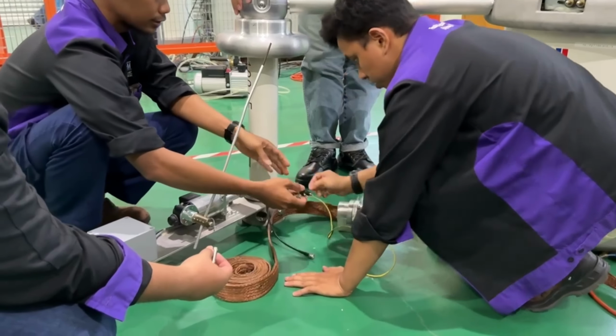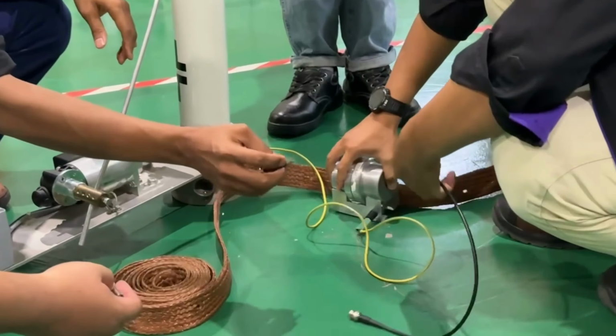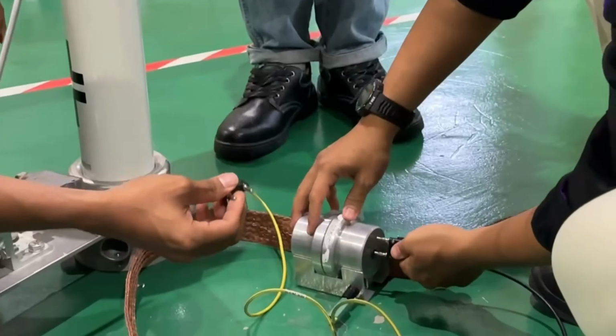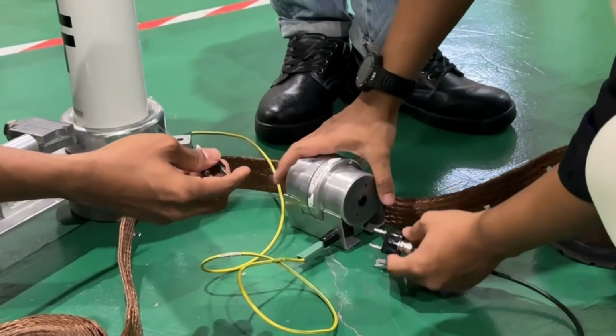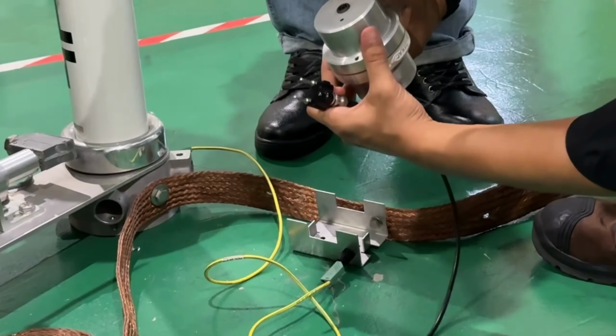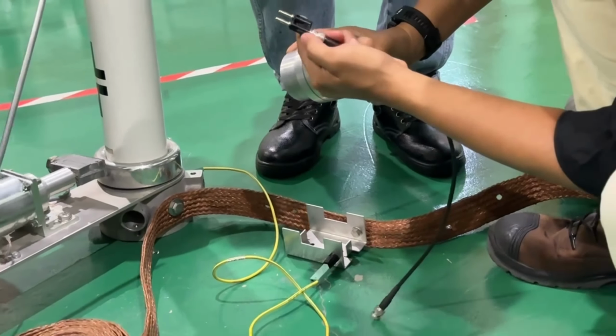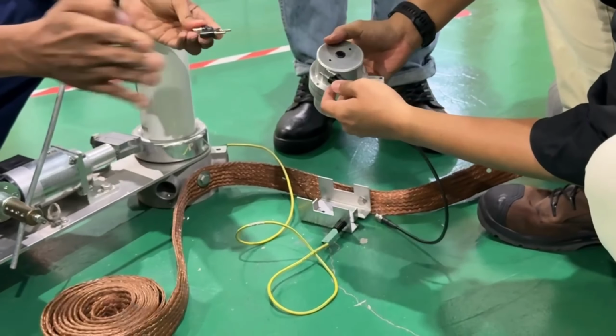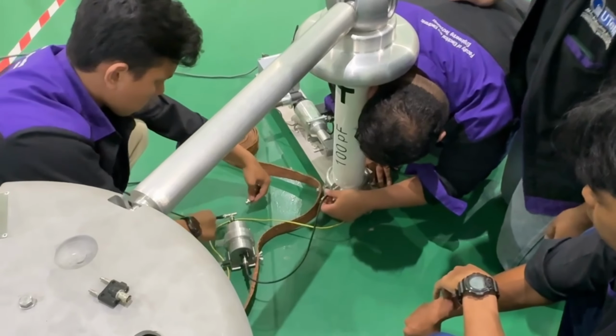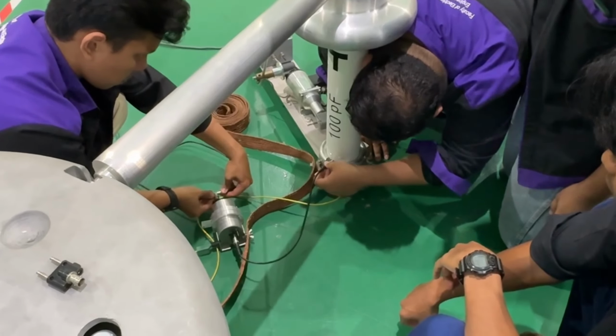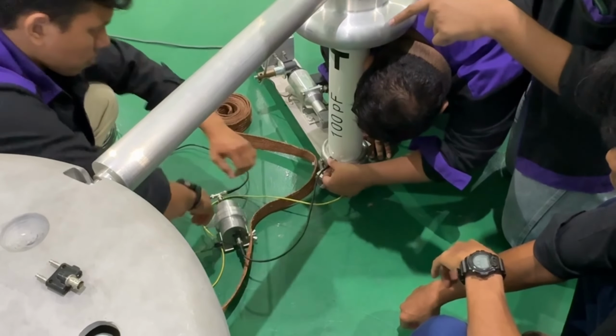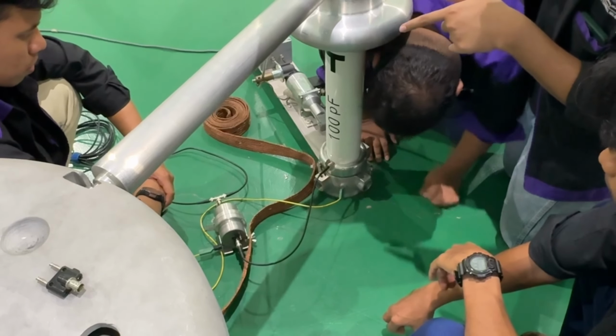So for the CB impulse connection, connect the male coaxial cable with the capacitor. Locate the two ports of the CB impulse unit. At the first port, insert the black connector. Connect a male connection cable to the black connector. Make sure a 100 picofarad capacitor is connected in series with the coaxial cable at this point.